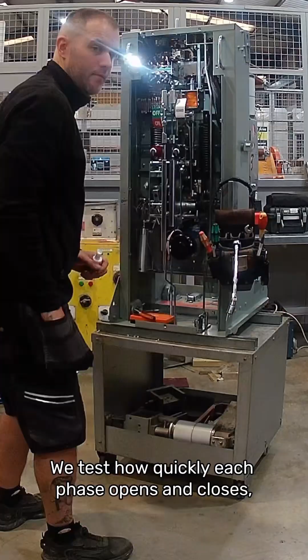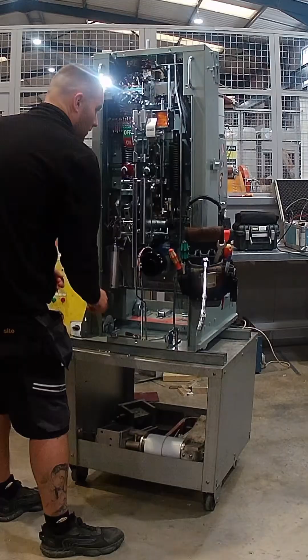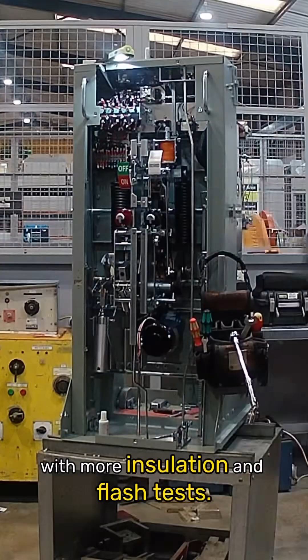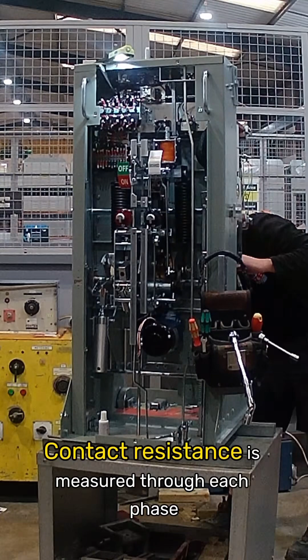We test how quickly each phase opens and closes, then check the internal wiring with more insulation and flash tests. Contact resistance is measured through each phase to make sure power flows cleanly.